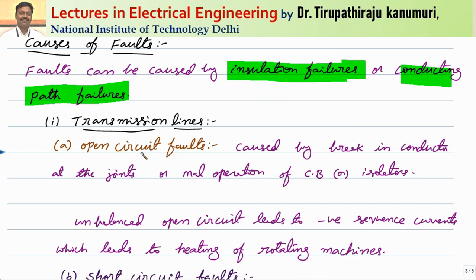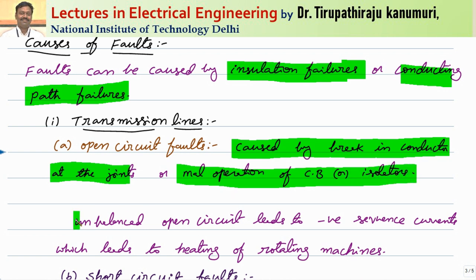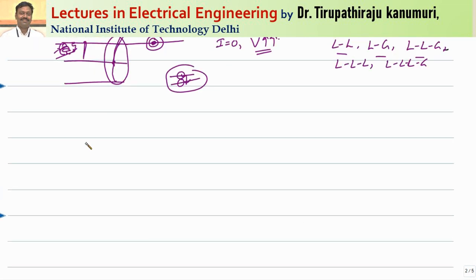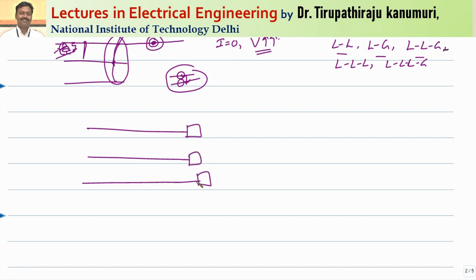Taking the transmission line, it can have two things: either open circuit fault or short circuit fault. Open circuit faults are caused by breaking of the conductor at joints, or mal-operation of circuit breakers or isolators. For example, in a three-phase system with three adjacent conductors and a circuit breaker in between, if during some operation two circuit breakers have closed but one has not, current will pass in those two phases but not the third.